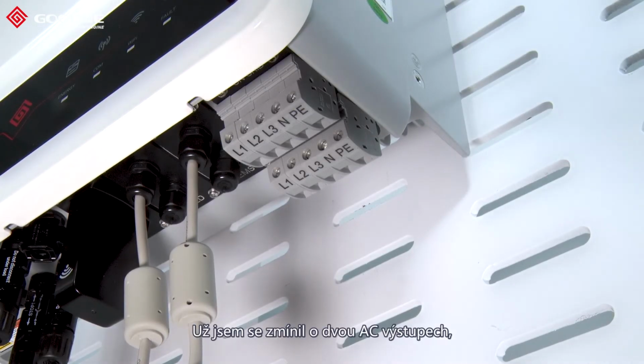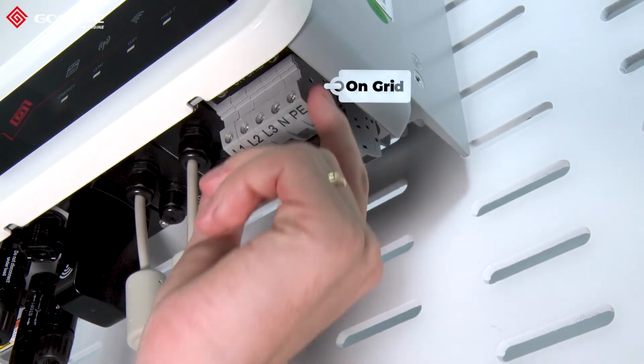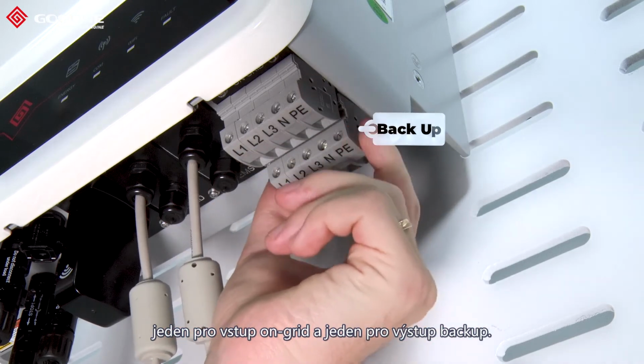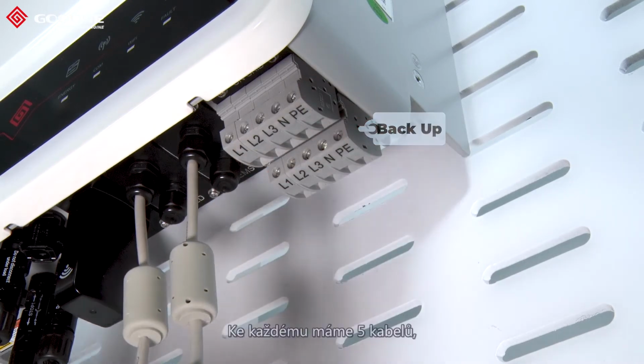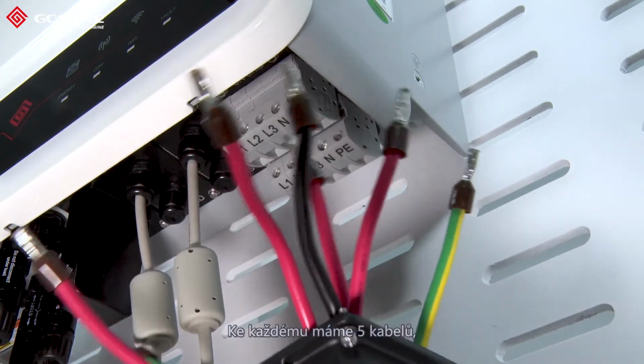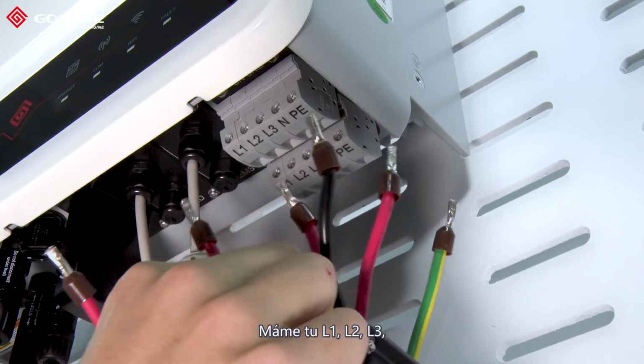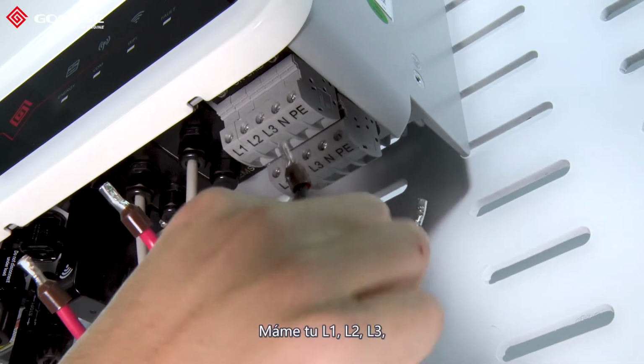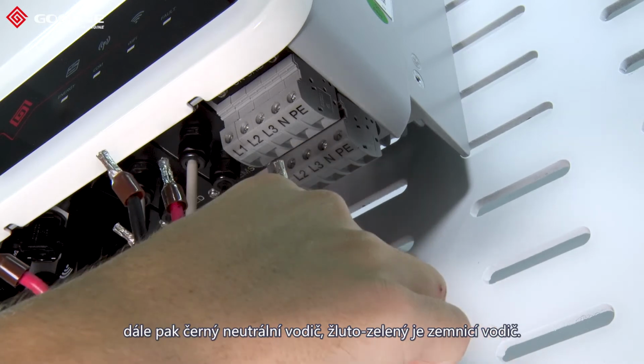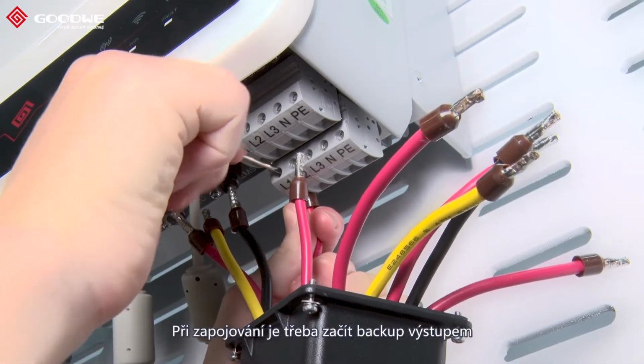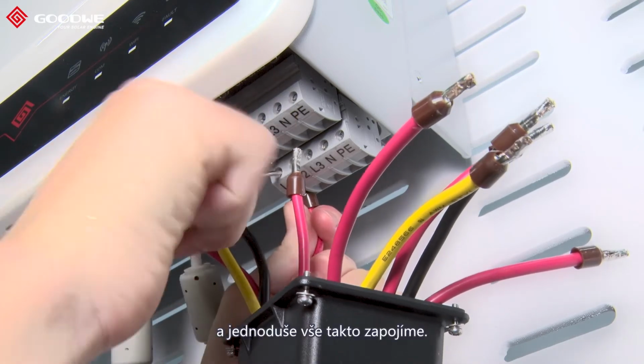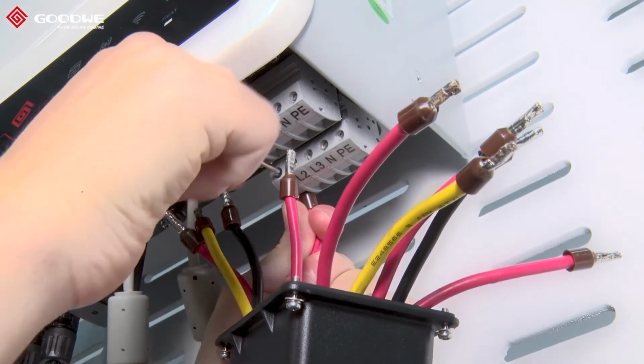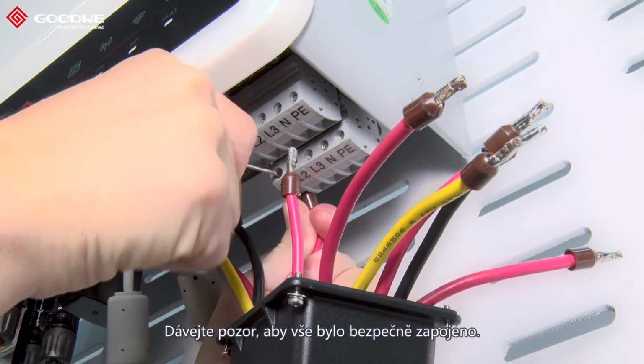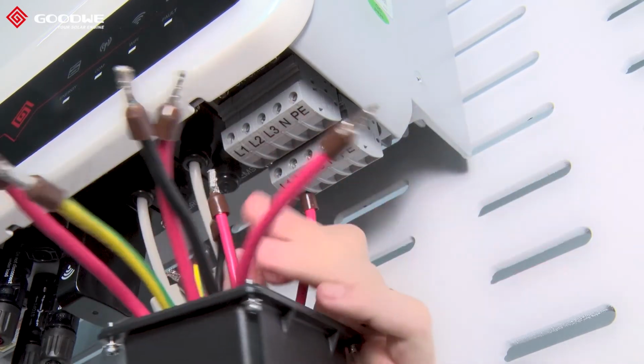As we just mentioned, we've got 2 AC outputs, 1 for the on-grid and 1 for the backup, and we've got 5 cables for each one. We've got the L1, L2, L3. The black one is the neutral cable, the green and yellow is the PE grounding cable. You need to make sure we start from the backup and we just connect them like so, and make sure they're safely connected.